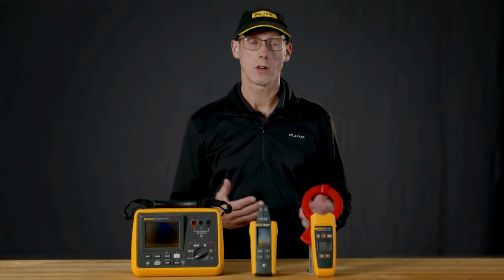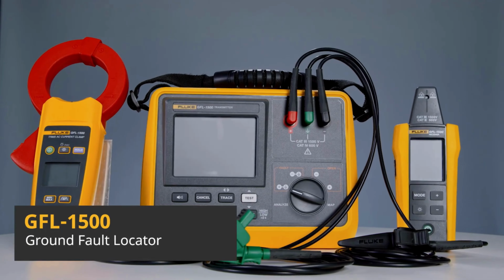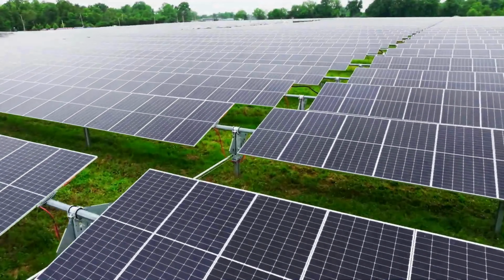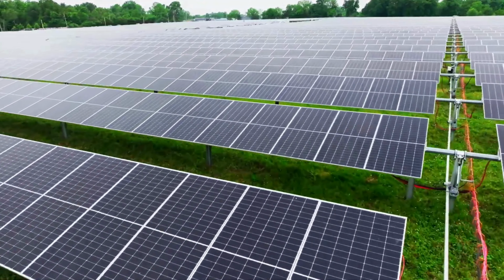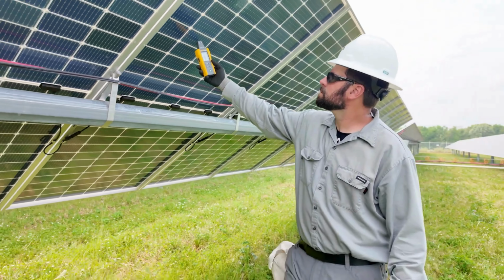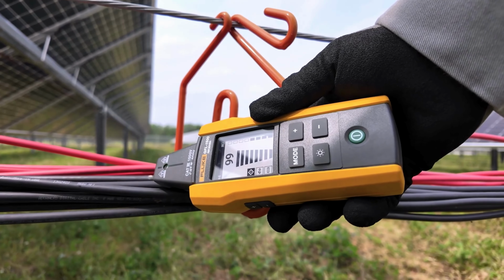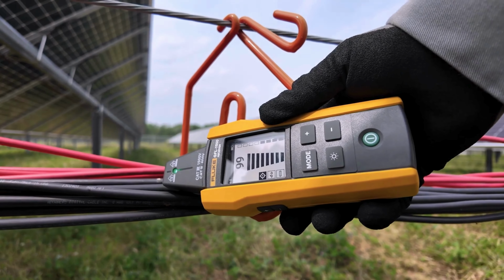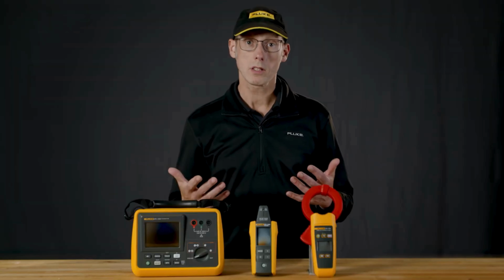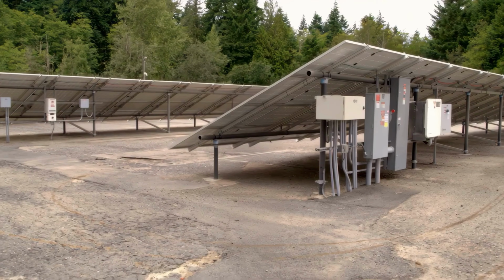And in this video series, we're going to be discussing the GFL-1500 ground fault location tool. Ground faults are a pervasive problem in solar installations, especially in the DC array, and this is a new technology to the industry that will allow technicians to identify and locate ground faults much more quickly than previous technologies that they've had access to.